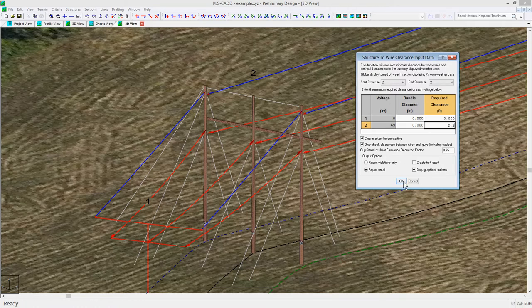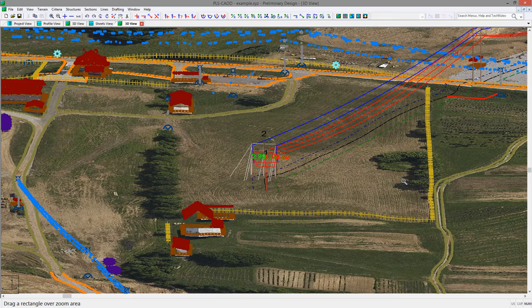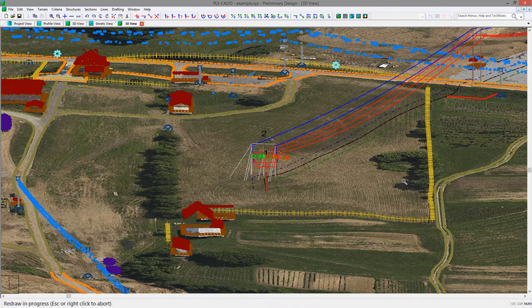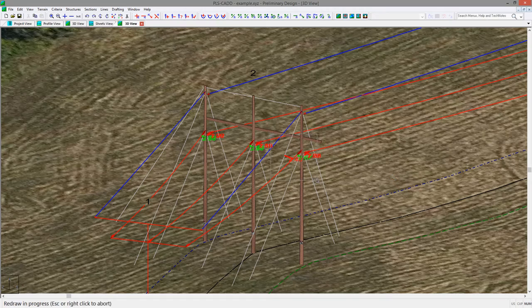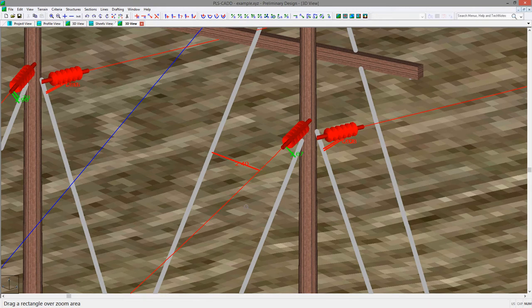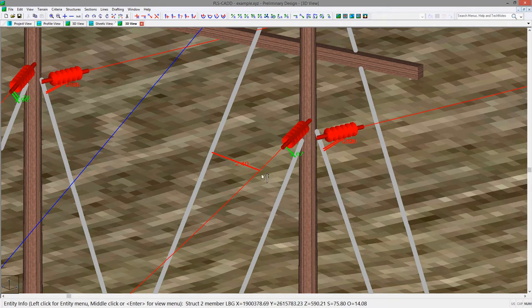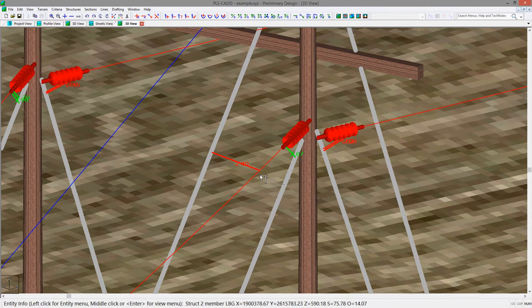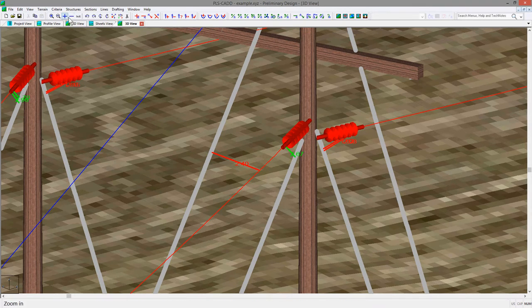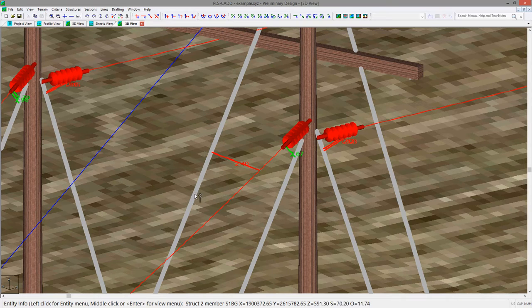After running the command, you can then zoom in on the structure and you will see that the required clearance of 2.5 feet is not met in several instances. We'll focus on just the one guy for this example where the clearance is 2.4 feet. If we were to insert a guy strain insulator in this area, it would reduce the clearance requirement by the input reduction factor.